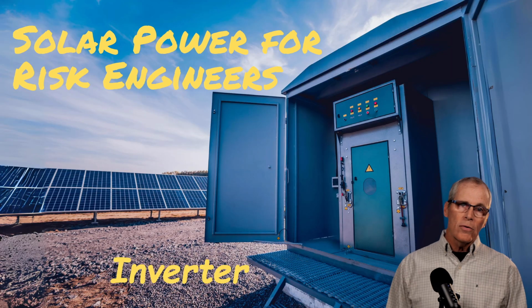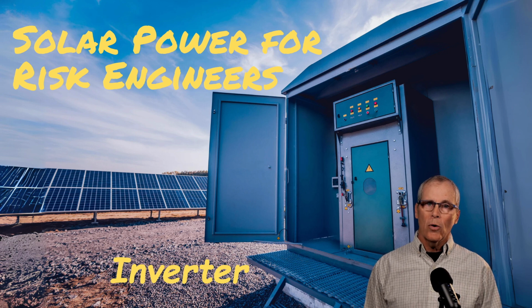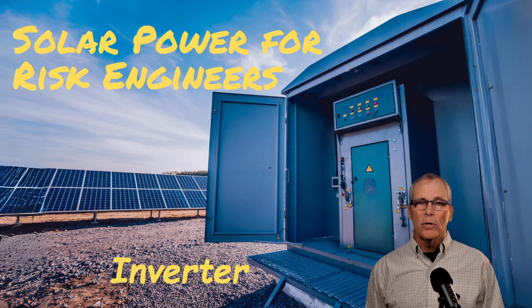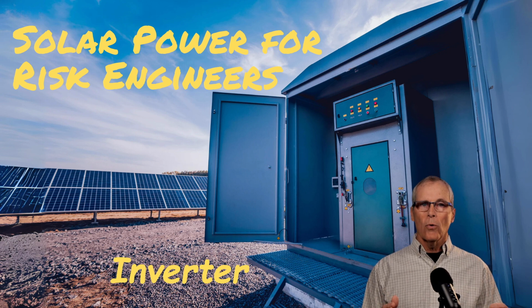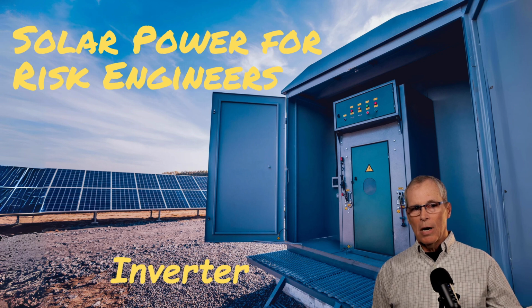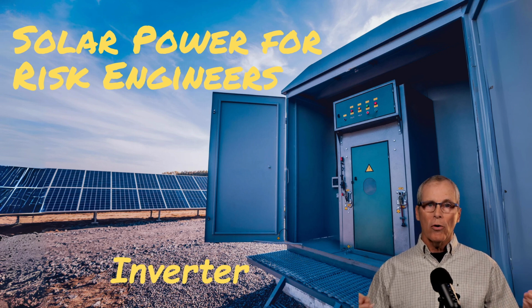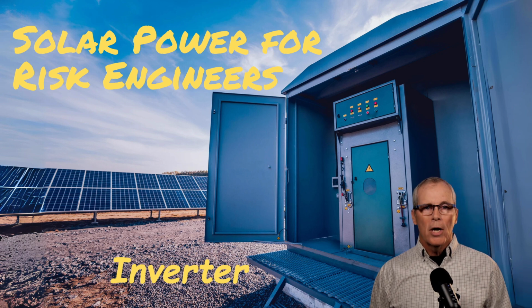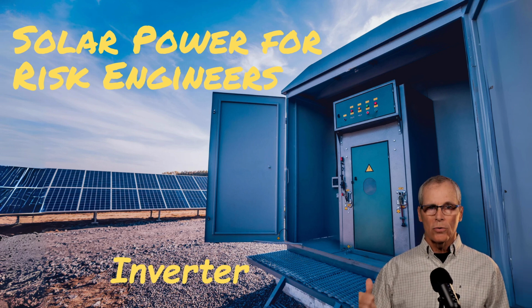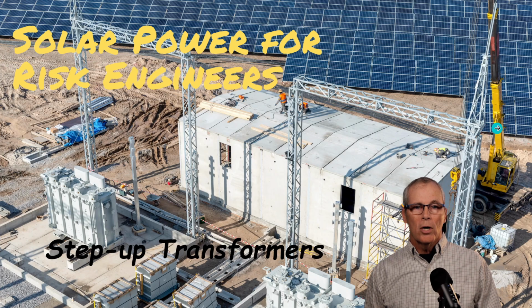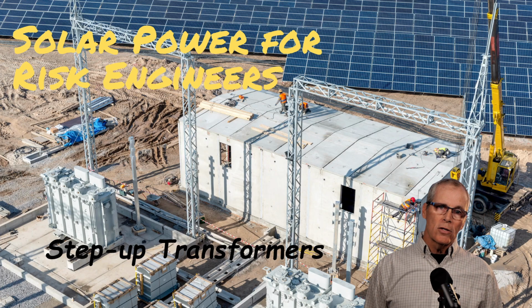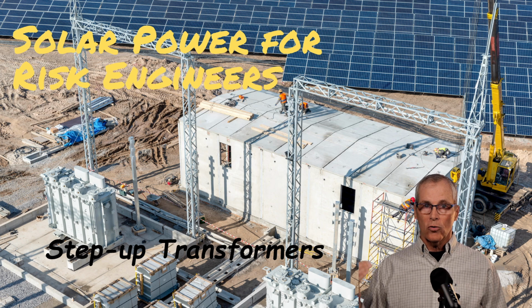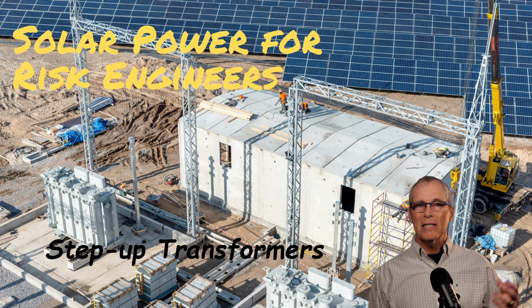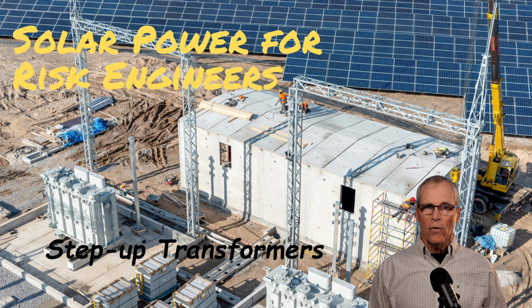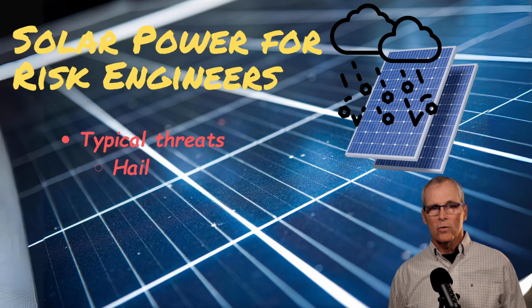So after the solar modules, the power that comes out of the modules is direct current, so we need to invert that to AC current. There's actually one step before that, called the combiner. The modules are in strings, and the strings all get combined before they go to the inverter, and then the inverter converts that DC voltage to AC, and then the AC voltage gets over to our step-up transformers, and then it gets elevated to the grid voltage so it can be transmitted across the grid. That's the basic components of a solar farm, not to mention the control room and the control buildings.